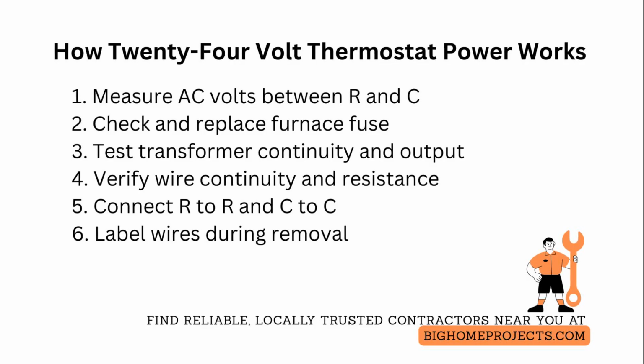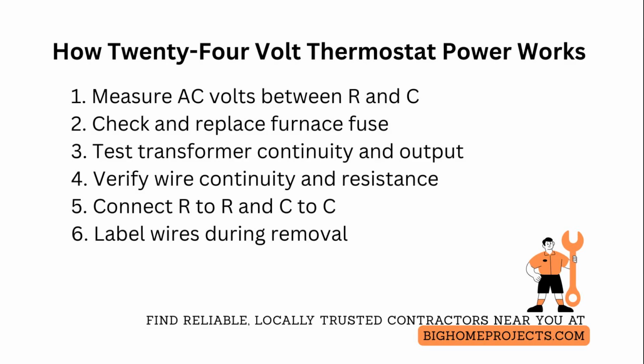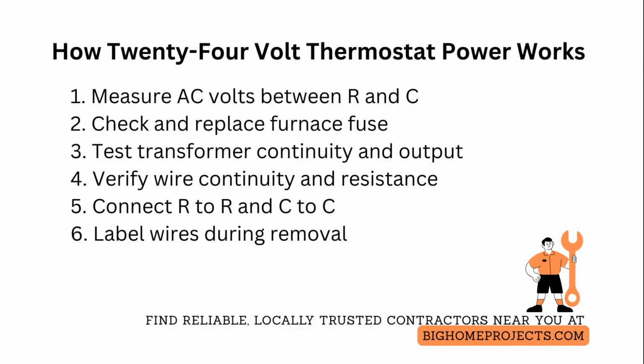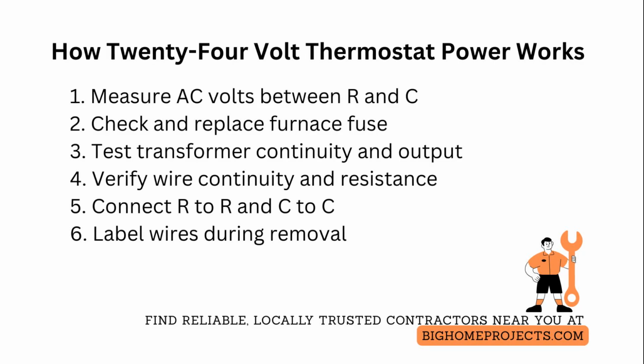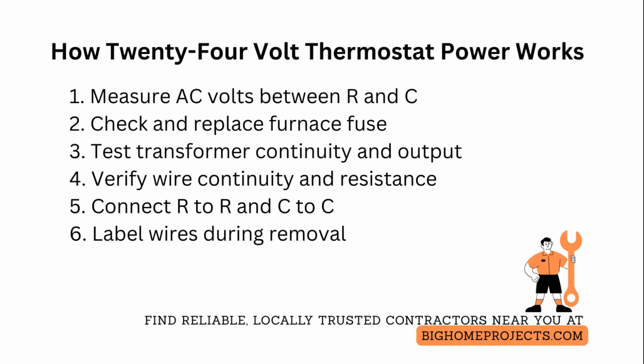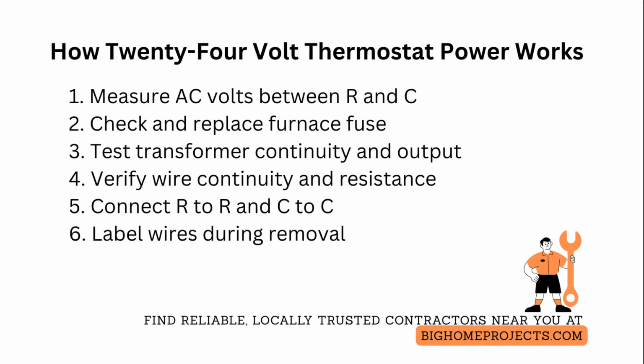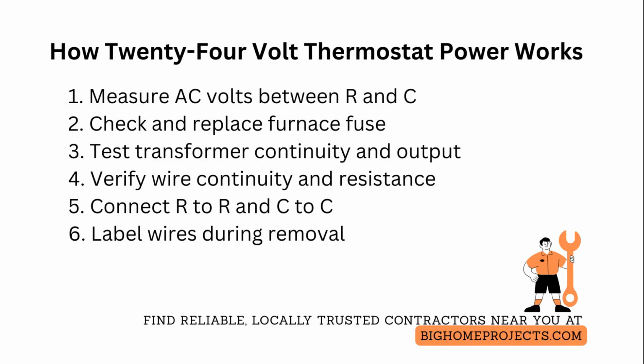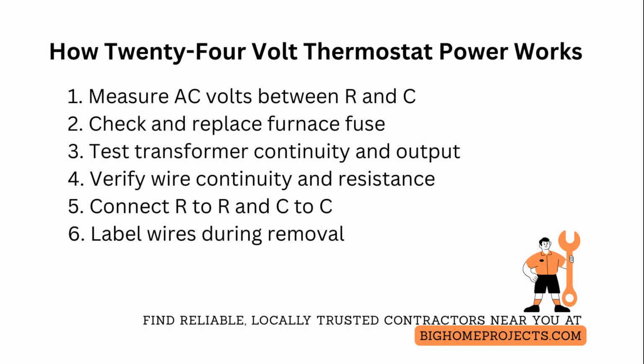Label each wire during removal to prevent miswiring when reconnecting, and route any new cable in parallel with existing low voltage bundles to minimize induced noise and ensure consistent shielding from electromagnetic interference. Use silicone-filled terminal blocks or manufacturer-approved wire nuts on all low-voltage splices and keep total run length and voltage drop in mind. Long runs over 100 feet may need heavier gauge wire to maintain reliable 24-volt delivery. Always turn off furnace power at the main switch and verify de-energized circuits before touching the control board to avoid shorting the transformer or causing erratic readings.